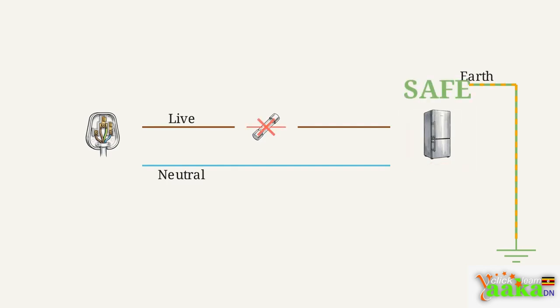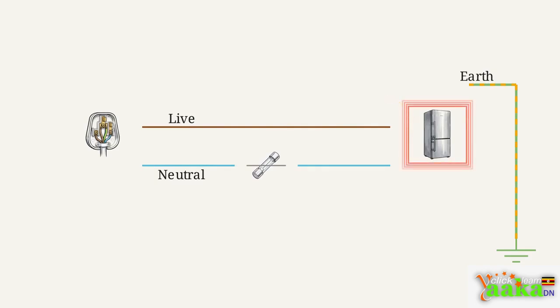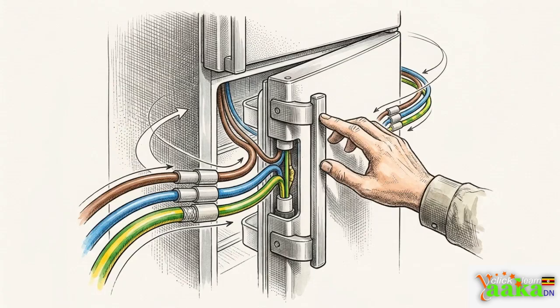That surge of current instantly melts the fuse, breaking the circuit. We always place the fuse on the live wire, so that when it blows, the high voltage supply is physically disconnected. If the fuse were on the neutral wire, the device would remain live and dangerous even after the fuse had blown. Proper wiring doesn't just protect the appliance, it is designed to isolate the user from the high potential energy source during a fault.